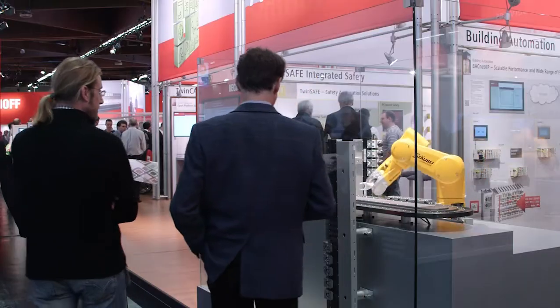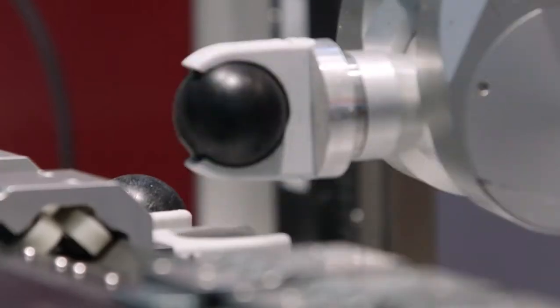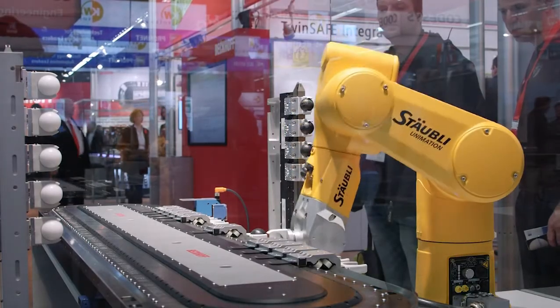The TwinCat3 software enables new kinematic transformations which enable the integration of highly complex robotics functions into the control system. TwinCat3 kinematic transformation gives us the possibility to integrate different robot kinematics — customer-specific robot kinematics into the system. We can include Delta kinematics, SCARA kinematics, and also the Stewart platform in the TwinCat3 system.